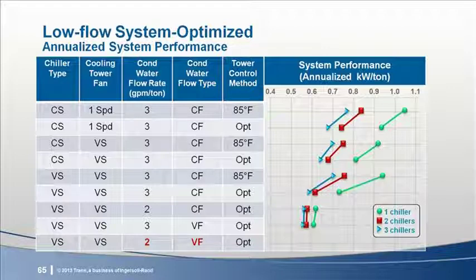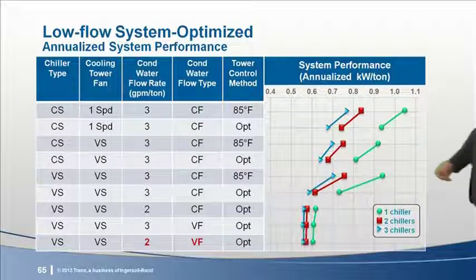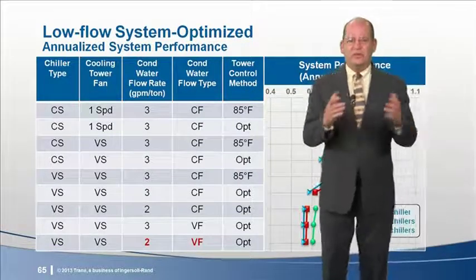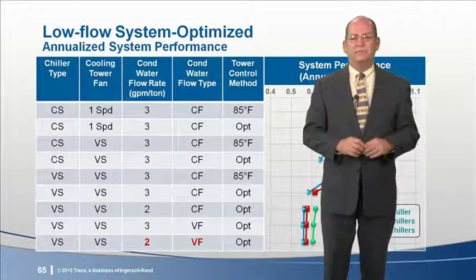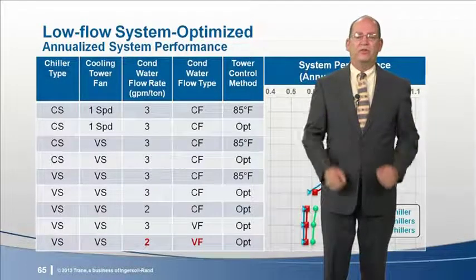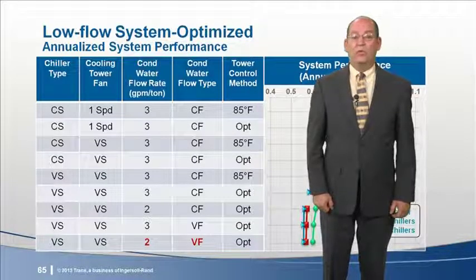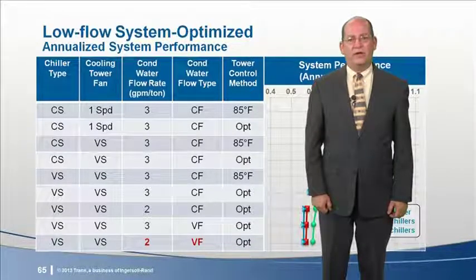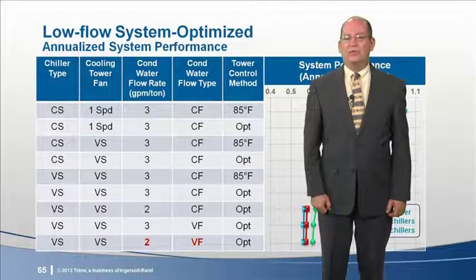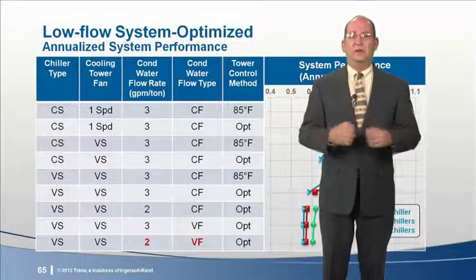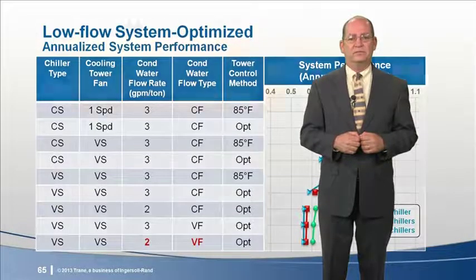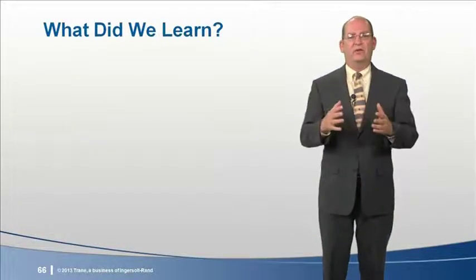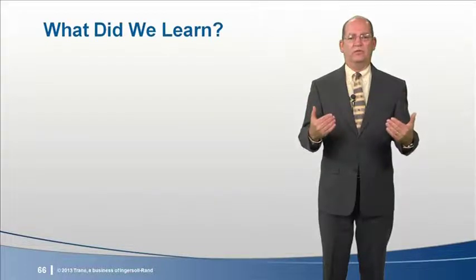The final option is design with a lower condenser water flow rate and optimize the condenser water pump control. So for the bottom points, the condenser design flow rate is 2 GPM per ton, and a VSD has been applied to the condenser water pump. As expected, the system performance is better, but only a little bit. So as Susanna mentioned when summarizing the 2011 E&L, reducing condenser design flow rate may allow high performance without increasing condenser water control complexity. So going back to the previous conclusion for condenser water design flow rates.